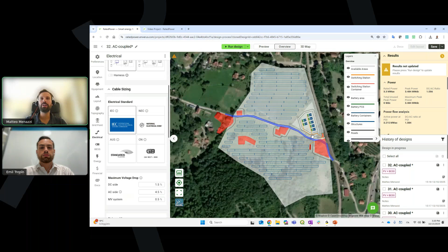In this overview tab, you can see the software can generate the low voltage AC cables connecting to my transformer station, the MV cables in orange going to the MV switchgear, and the string cables in yellow. All these cables are sized based on voltage drop, which you can customize, and current carrying capabilities. You'll get an Excel file with the length and cross-section of each cable.